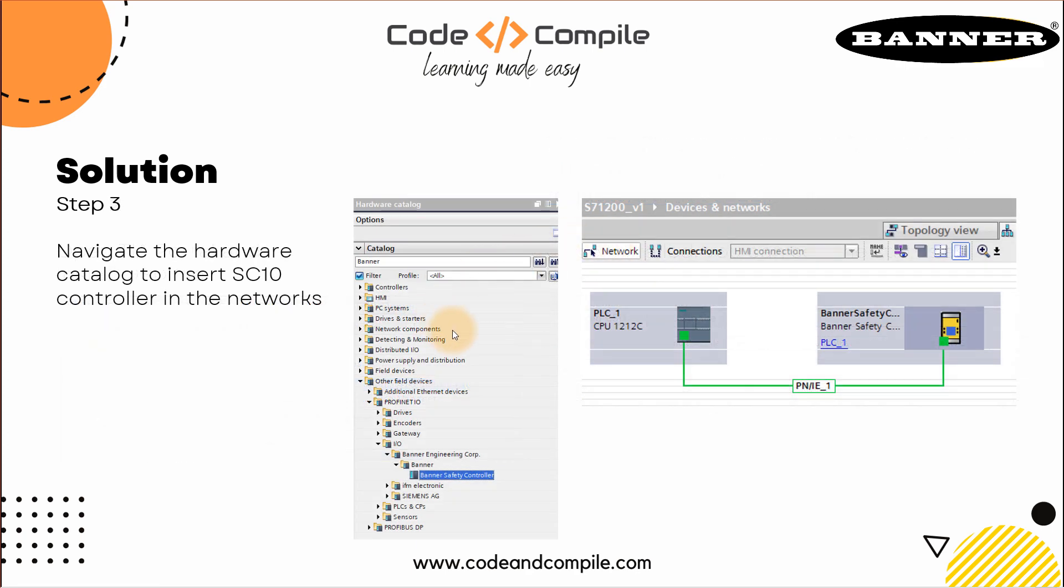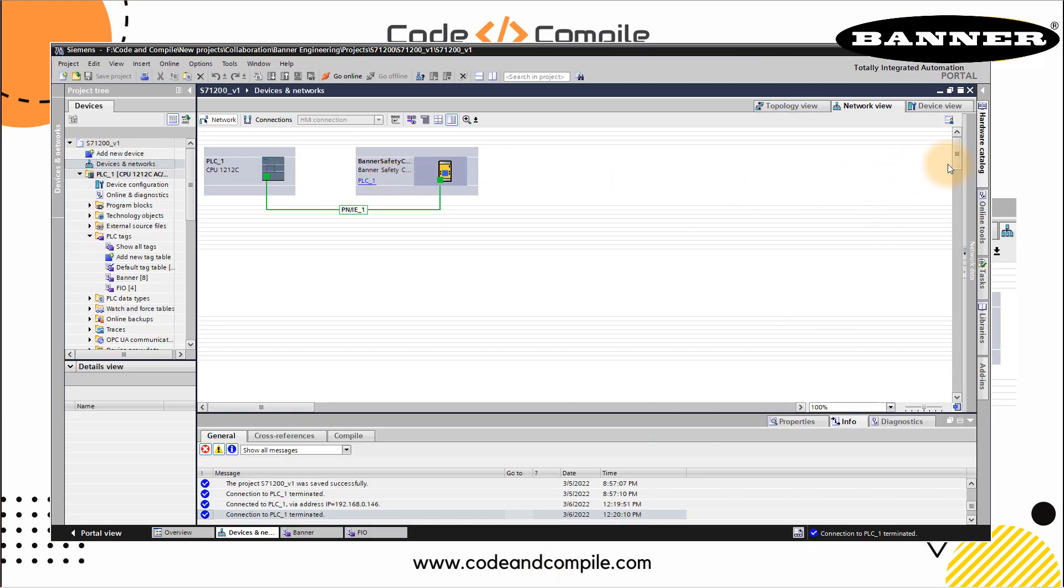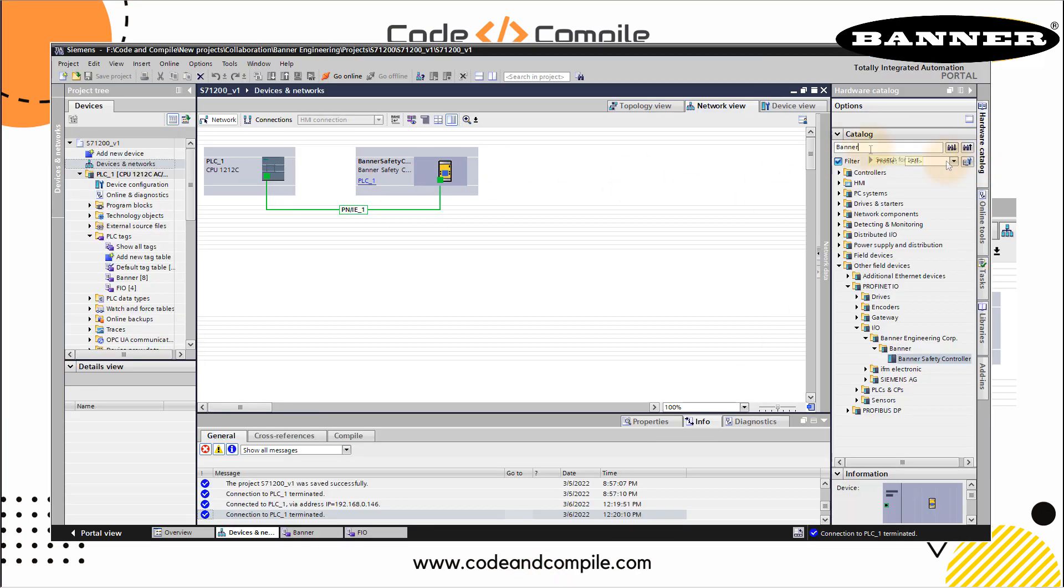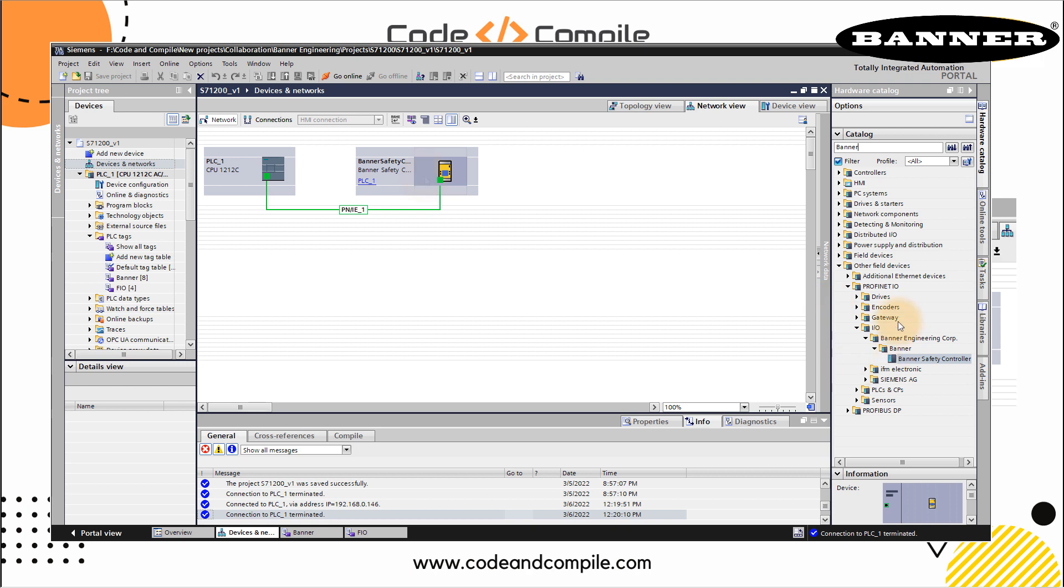Once this is done, we have to navigate to the hardware catalog. This you can find in the Siemens PLC program. Once the GSD file is installed, you can go to hardware catalog, type Banner and press Enter. Then you will see your Banner Safety Controller. All you have to do is just drag and drop in your network window. Once you do that, this hardware catalog is here. Once you have this here, you just have to connect these together.